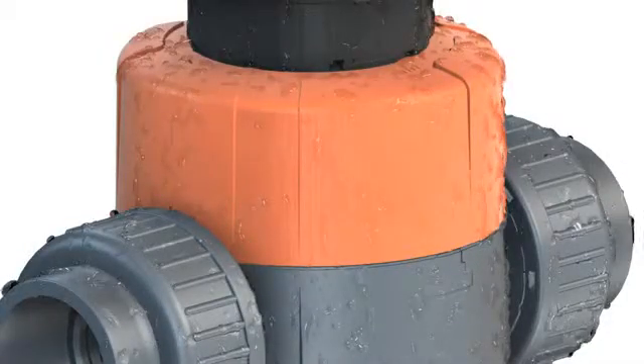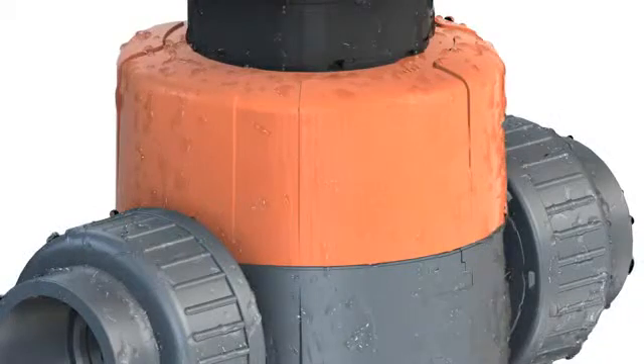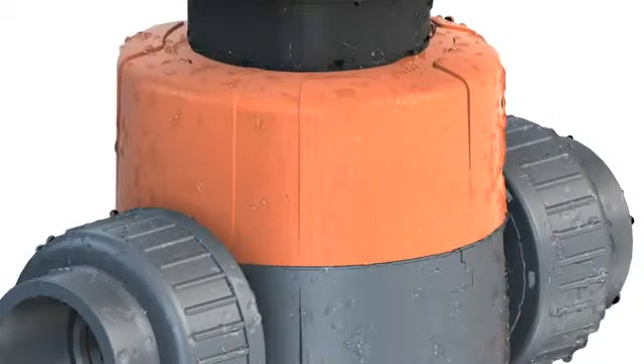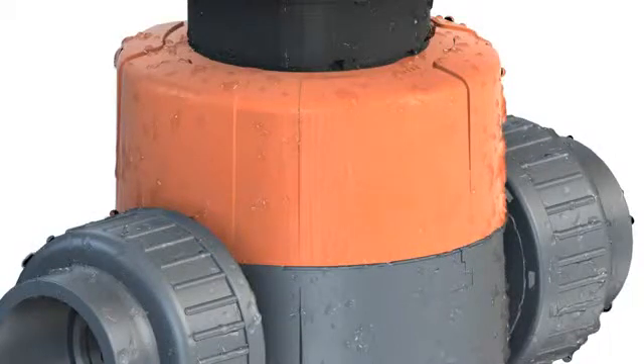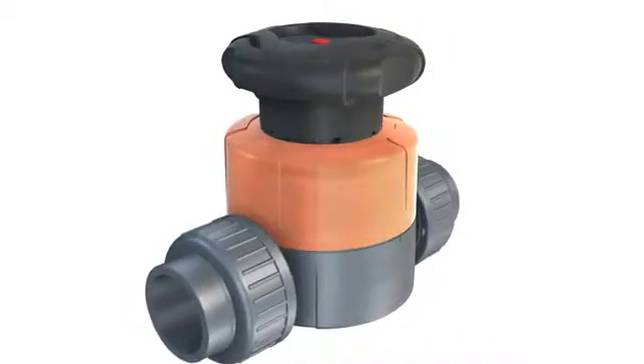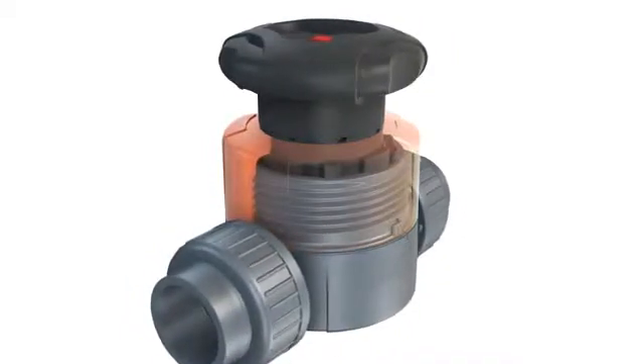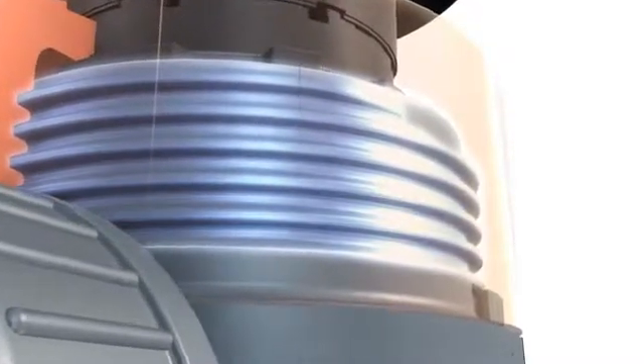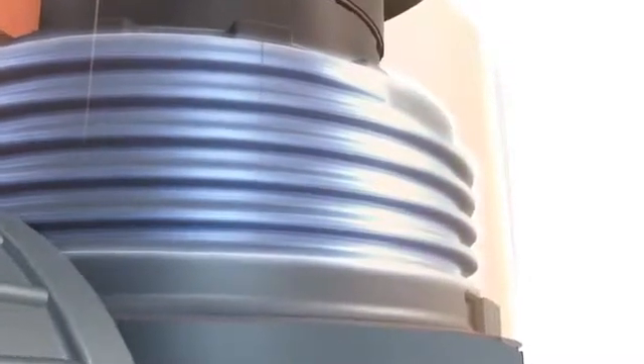No metal, no corrosion. The core thread between the valve bonnet and base is constructed entirely without metal. This proven design using only one housing nut has been used successfully on union joints for decades. Leakage caused by varying degrees of thermal expansion is eliminated.